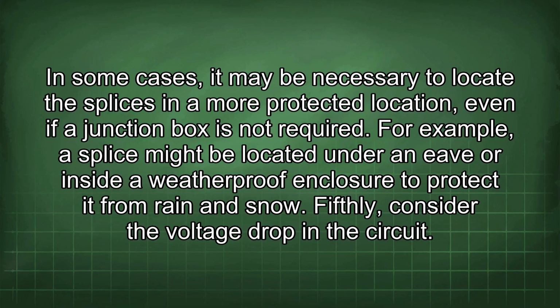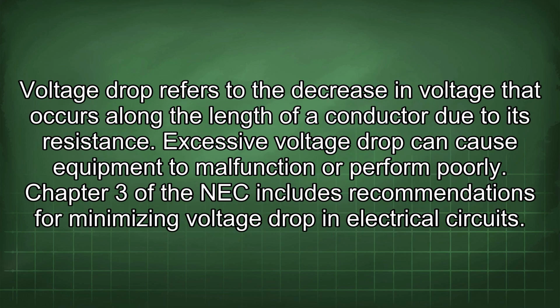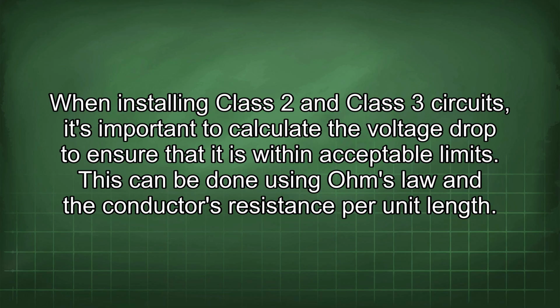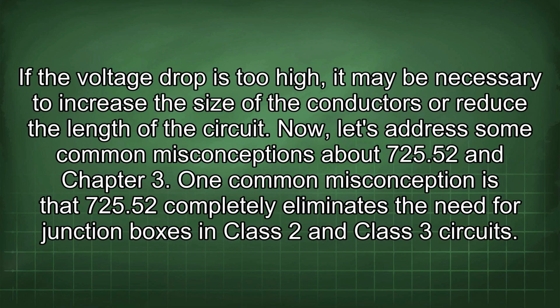Fifthly, consider the voltage drop in the circuit. Voltage drop refers to the decrease in voltage that occurs along the length of a conductor due to its resistance. Excessive voltage drop can cause equipment to malfunction or perform poorly. Chapter 3 of the NEC includes recommendations for minimizing voltage drop in electrical circuits. When installing Class 2 and Class 3 circuits, it's important to calculate the voltage drop to ensure that it is within acceptable limits. This can be done using Ohm's law and the conductor's resistance per unit length. If the voltage drop is too high, it may be necessary to increase the size of the conductors or reduce the length of the circuit.